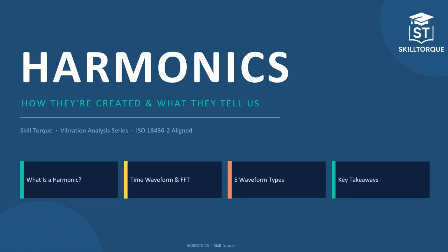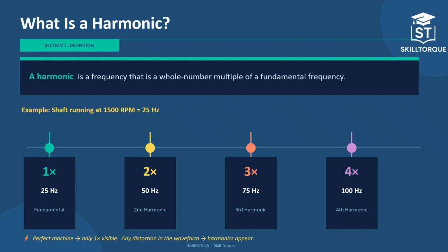Okay, so let's start with the basics first. The first thing that we are going to discuss is what harmonics are. A harmonic is a frequency at a whole number multiple of the fundamental, or you can say an exact multiple of the fundamental. Now you will say, what is this fundamental? The fundamental is also known as 1x, or you can say it's the shaft running speed. Everything else is a multiple of it.